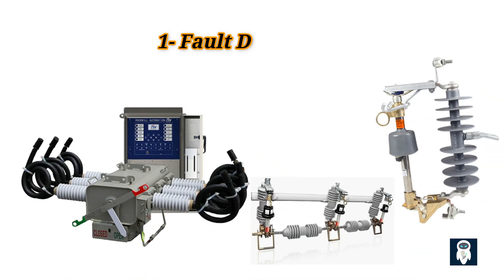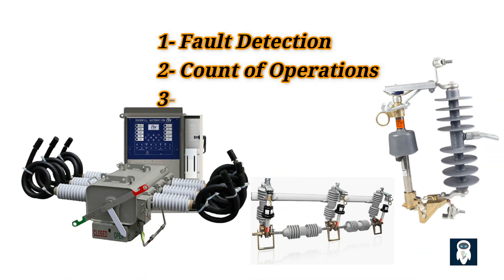Now let's break down the process. Step 1, fault detection: when a fault occurs, such as a short circuit, the sectionalizer senses the abnormal current flow. Step 2, count of operations: unlike circuit breakers that trip immediately, a sectionalizer counts the number of fault currents it experiences. It typically waits through a preset number of operations.